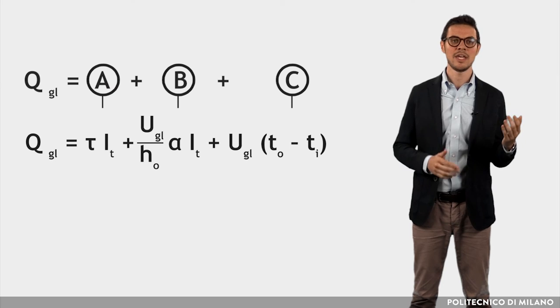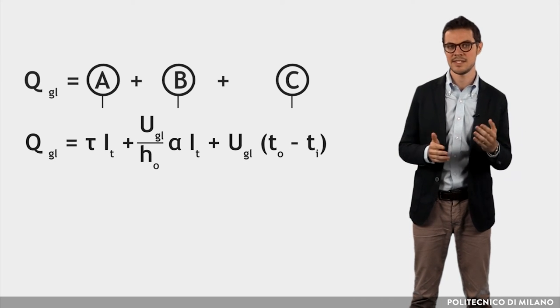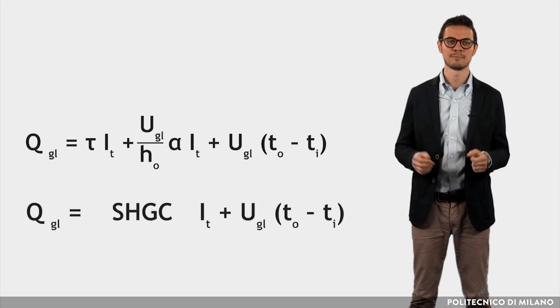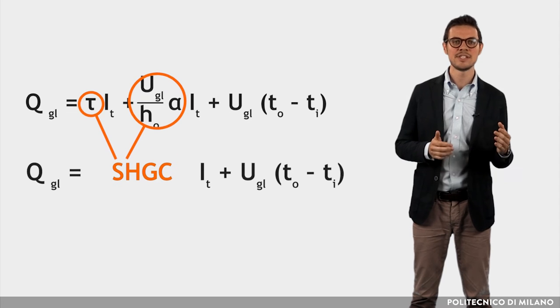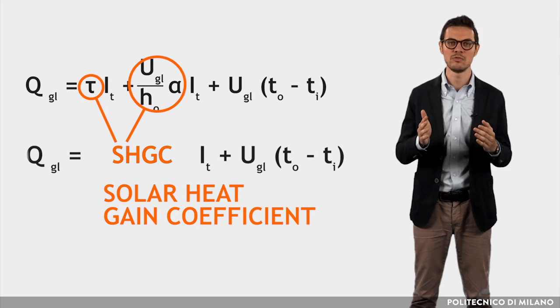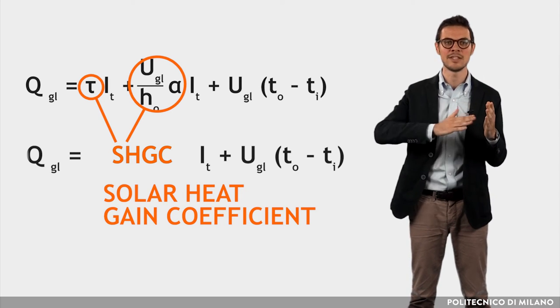Since the terms A and B are linked to solar radiation, while C exists even in its absence, the equation can be written in this way, where SHGC is the solar heat gain coefficient, characteristic of each type of fenestration, which varies with the incident angle.